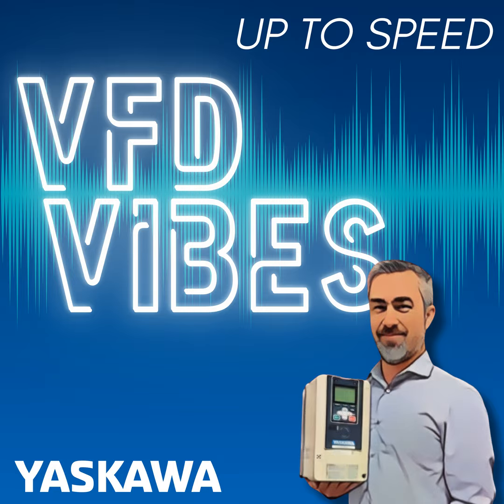There's a couple parameters you have to enter, such as motor horsepower and amperage. And then you do your auto tune. It's going to sit idle. It's not going to spin. And then you'd have a base stationary tune in there, and you're good to go probably from that point on.